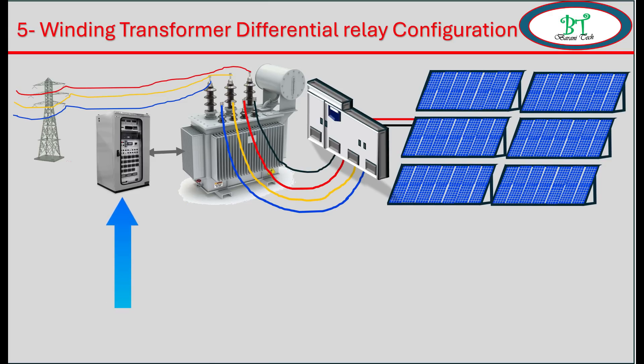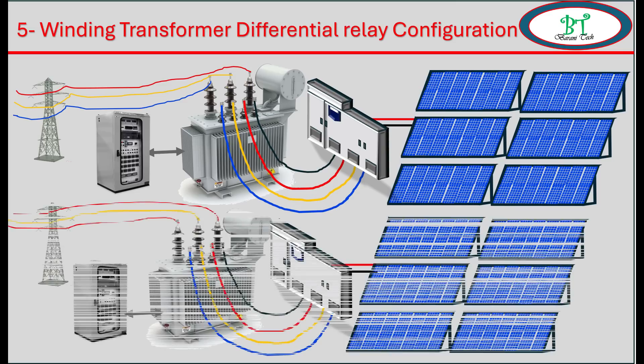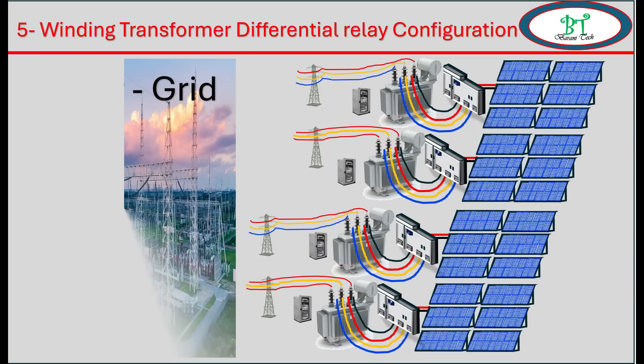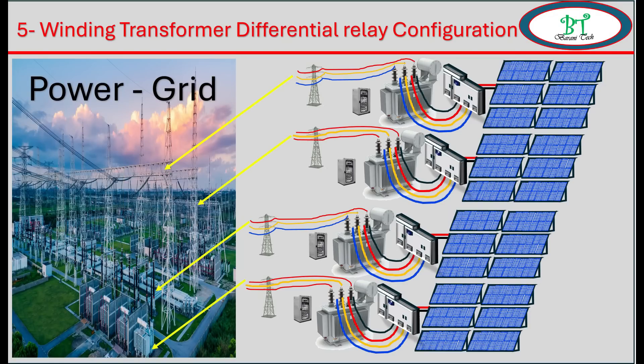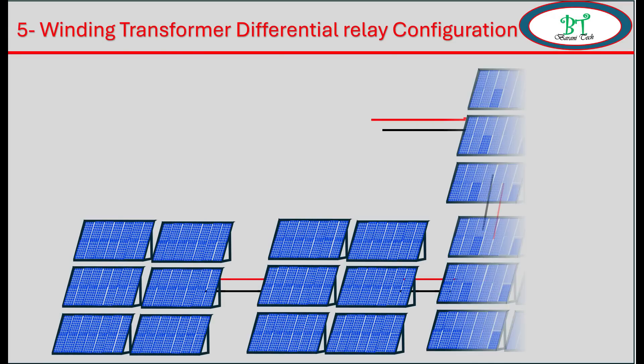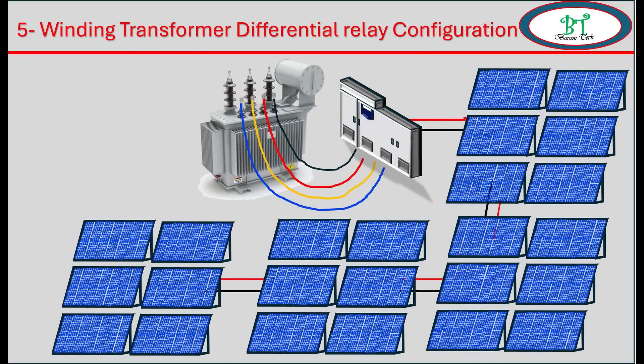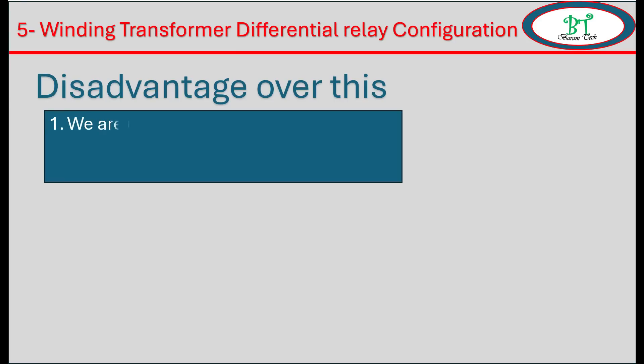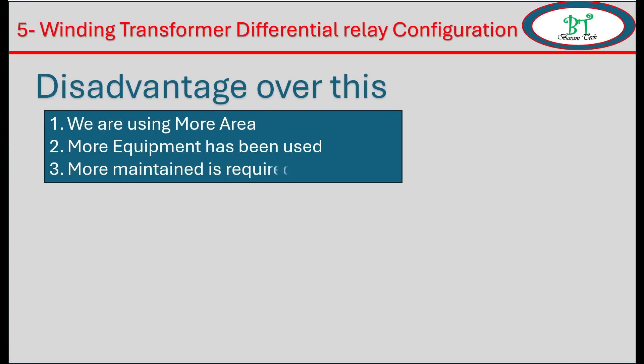For this transformer, there will be one protection panel associated with HV CT, LV CT, and VT. This setup can be used in a small-scale power plant. If your power plant is very big, we need many similar setups. Using many solar arrays with one power module makes the cost and loss very high. Disadvantages include: more area used, more equipment required, and higher maintenance cost.